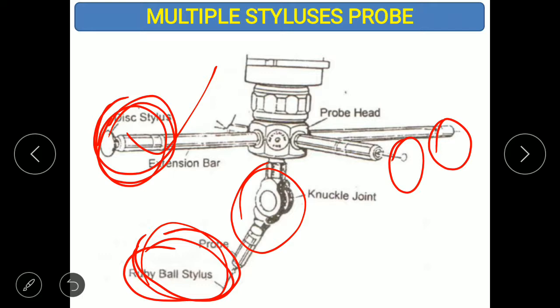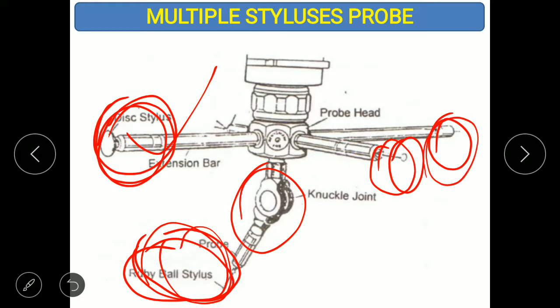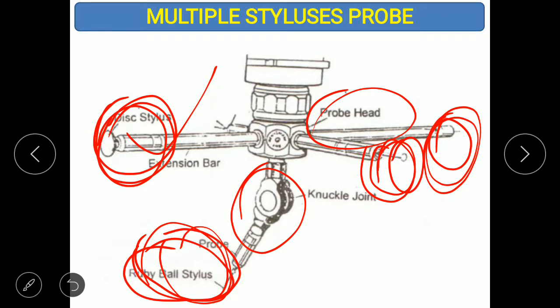If you have a multiple stylus probe with different stylus types in the same probe head, you simply select the required stylus type and take readings — saving time. However, the multiple stylus probe is more costly because it includes many stylus types.